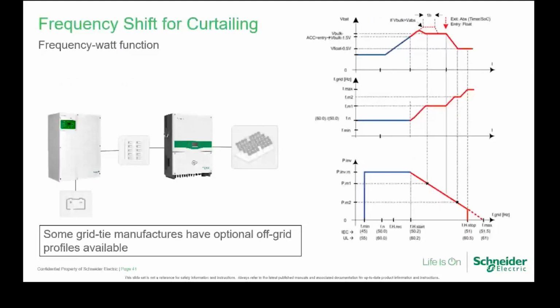Some grid-tie manufacturers have optional off-grid profiles available if you want to do a frequency shift. Depending on where you're located, they might have different profiles to suit. On some of our inverters, you might have to vary the ramp rate to make sure that you're not cycling too many times. So in this case it's 0.02 hertz per second until the battery reaches bulk, and 0.2 hertz per second when the battery voltage goes above 2 volts, so you reach the maximum charge, or the battery charge is higher than the maximum charge rate.